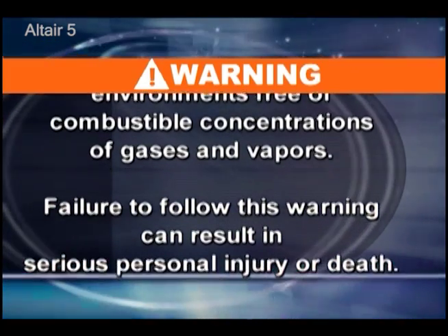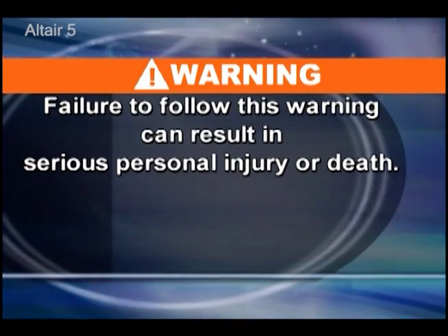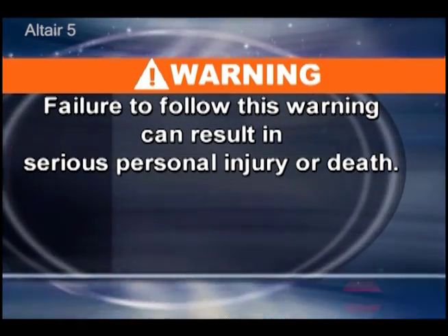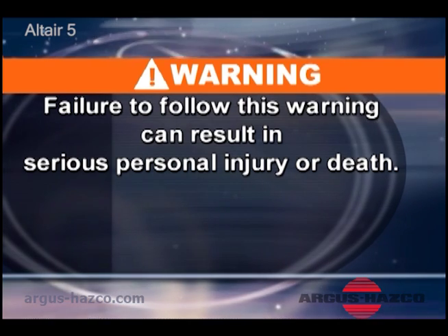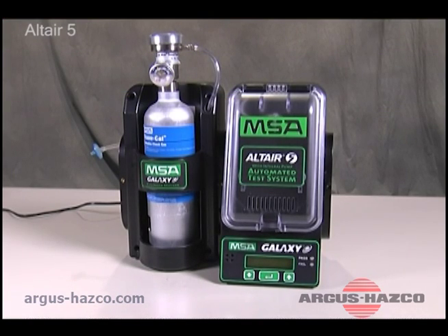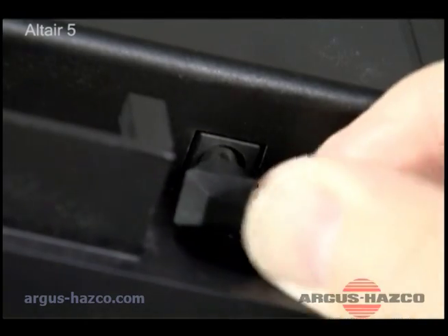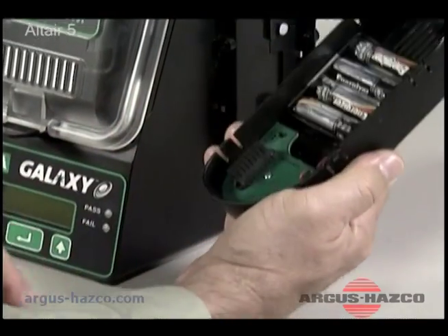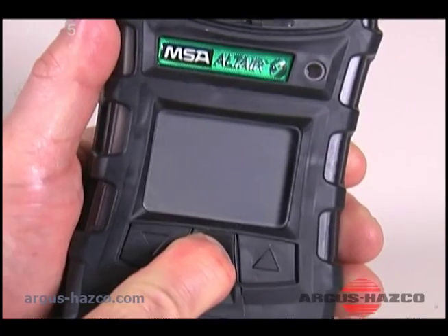Use the Galaxy system only in non-hazardous environments free of combustible concentrations of gases and vapors. Failure to follow this warning can result in serious personal injury or death. To test an instrument, make sure that the Galaxy test stand is connected to an adequate gas supply and is plugged in or powered by an optional replaceable battery pack.